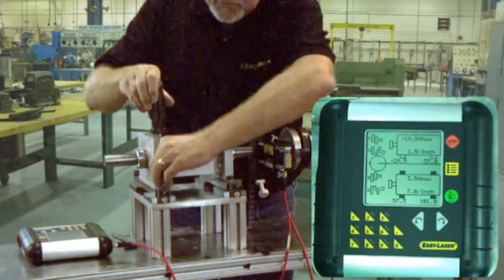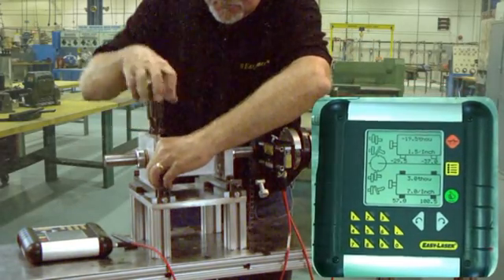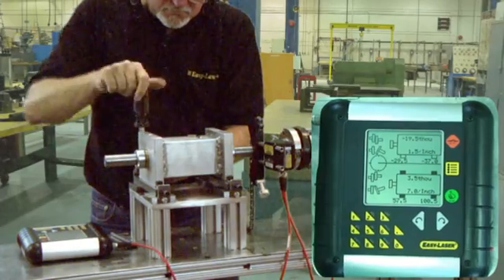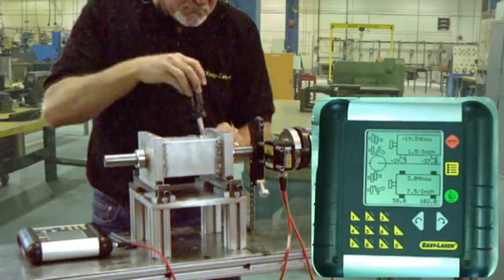We will now make corrections in the vertical plane. After loosening the bolts we can add the amount of shim shown on the screen to both the front and back feet of the machine.